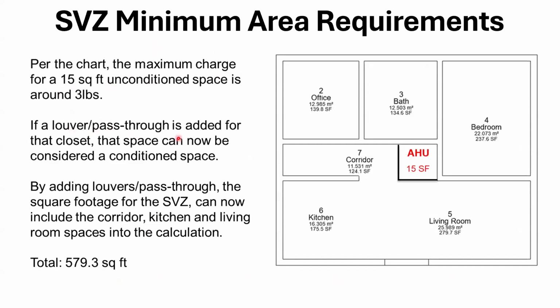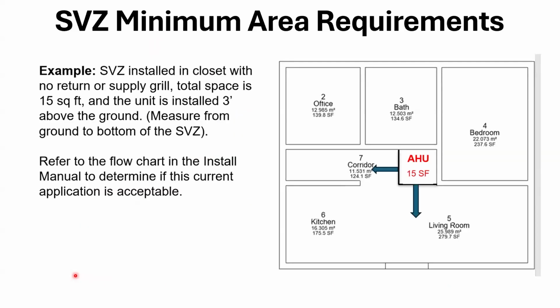If a louver pass-through grill is added for the closet, the space can now be considered a conditioned space. That's what I was talking about, right? Louvered grills, or louvered door, or transfer grills. We'll show that coming up here. By adding those, we can allow this extra square footage in the calculation, which would give us a total of 579 square feet now instead of 15.